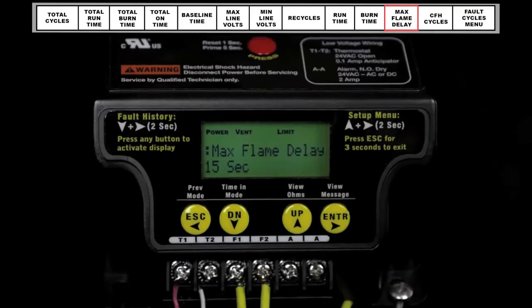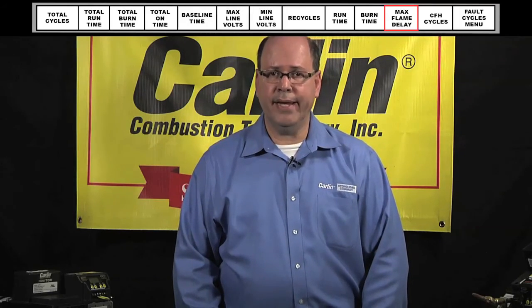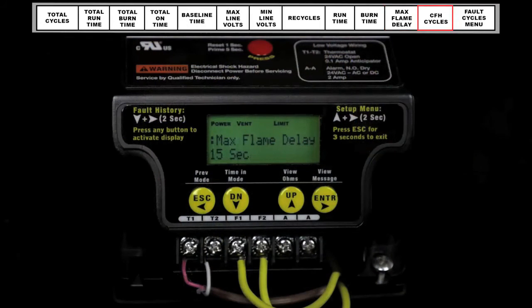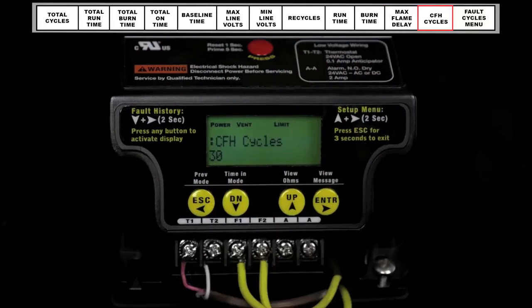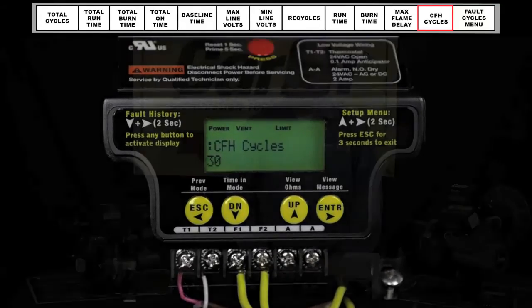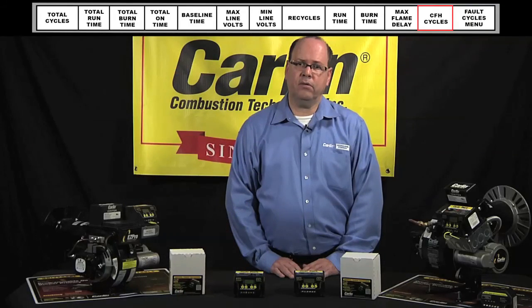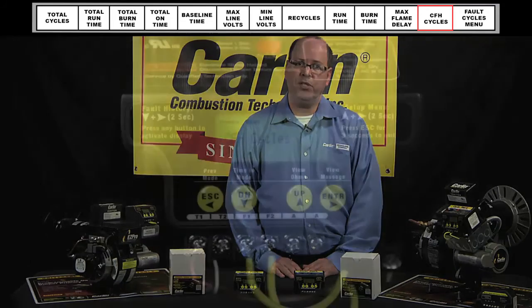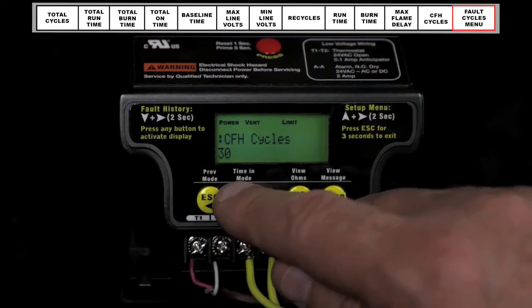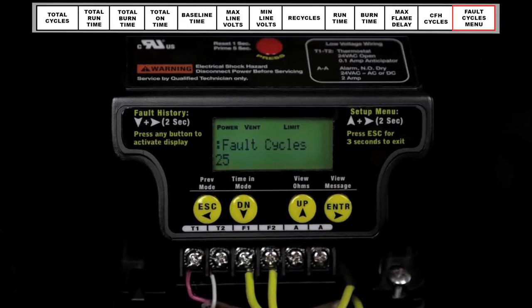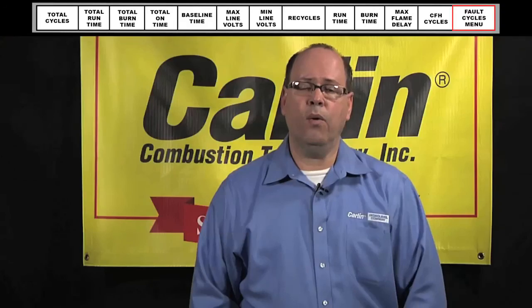This is a measured flame response time to when the oil valve opens. The maximum delay in sighting the flame is displayed here. This feature is very useful in diagnosing what the industry typically calls delayed ignition. Pressing down again, we come to our last feature, CFH cycles. This displays total call for heat cycles since the last baseline reset. When we press the down arrow again, this returns us to the fault cycles menu display. Now on to the next chapter.